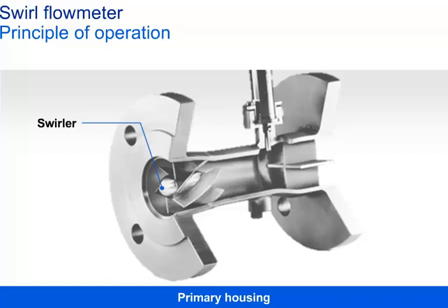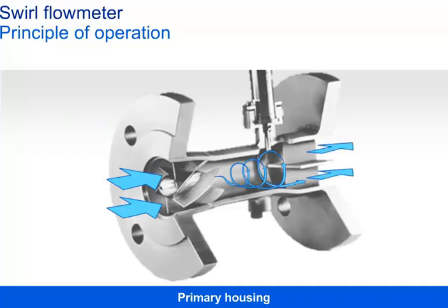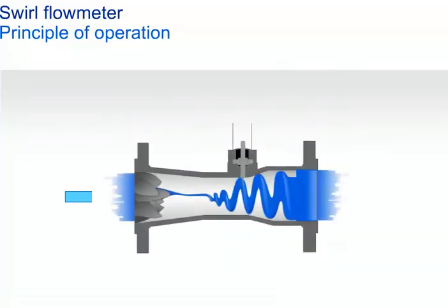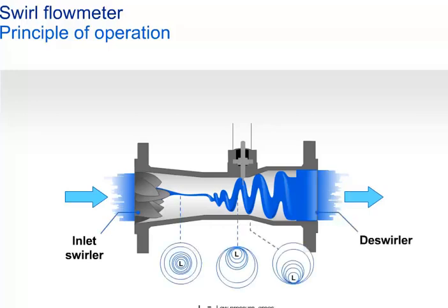In this case, however, the fluid is rotated by a swirler on the inlet side, and a sensor is used to determine the rotating frequency. The inlet guide body causes the axially entering flow to rotate. In the center of this rotation, a swirl core is formed, which, due to the backflow, is forced into a spiral-shaped secondary rotation. Inside this core, the pressure is very low, so that the sensor phases of high pressure and low pressure alternate with the rotation frequency.